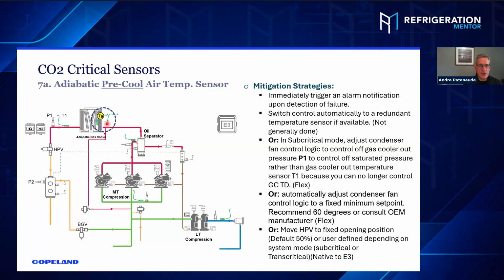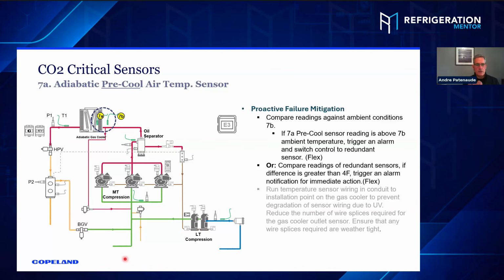Well, it might have been. So generally, this sensor 7B that we call it is the ambient sensor. And when it senses 80-degree ambient, pretty much all gas cooler manufacturers turn their fan full speed. Yeah. Okay. So they have that. And depending on this ambient sensor, they also activate water at a specific point, 70 to 75 degrees, depending on the manufacturer. So a little bit different setup depending on which manufacturer it is. And I've got a little bit of explanation on each manufacturer coming up. Well, three manufacturers.